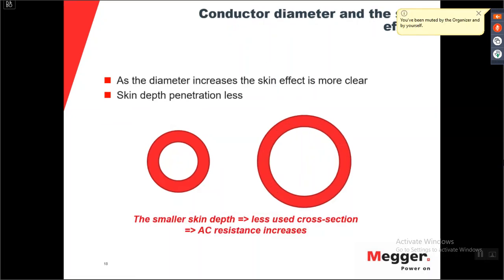Transformer, and we would like to have the transformer carry a larger current, then we need to increase the conductor size. So we go from this size to this size. But in reality, we will have a much larger area in the middle not carrying any current. So actually, it doesn't help us in carrying a larger current.